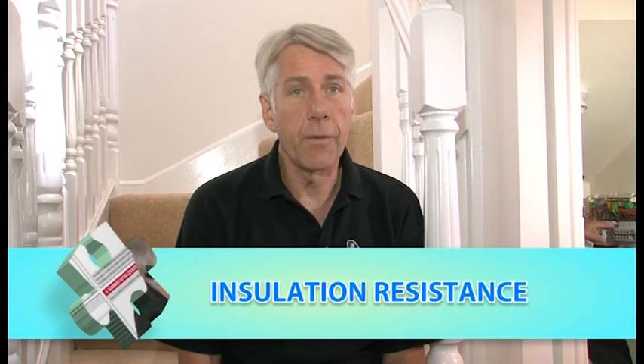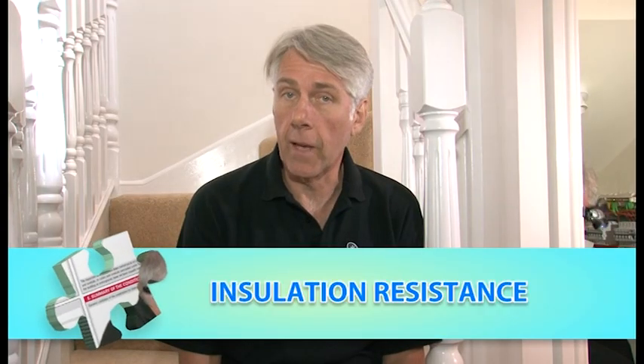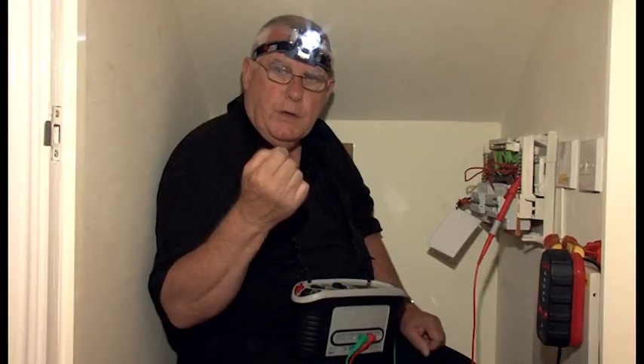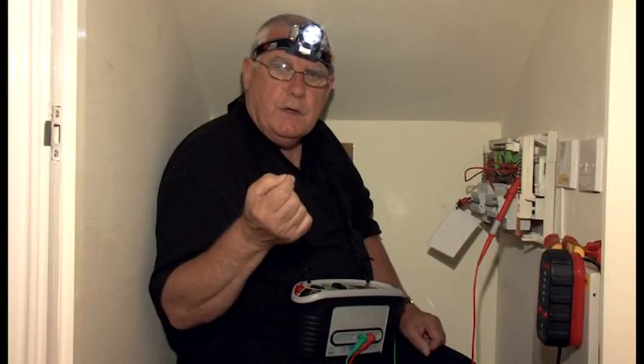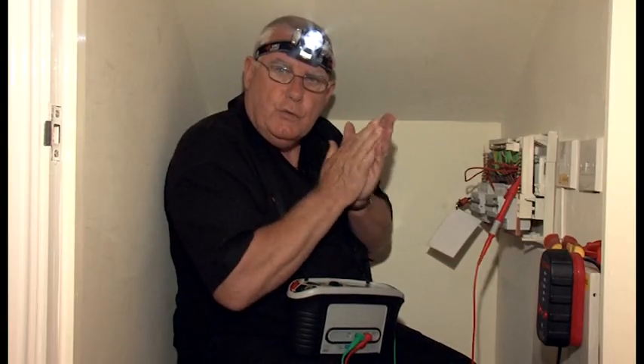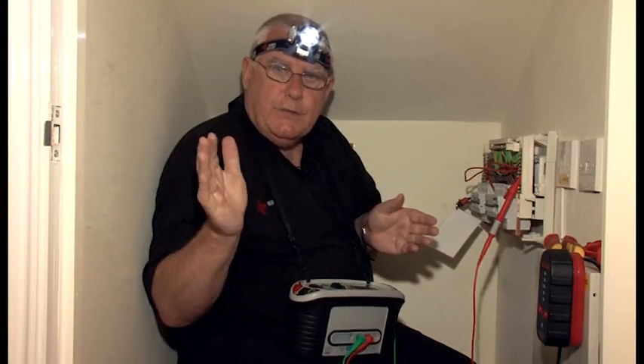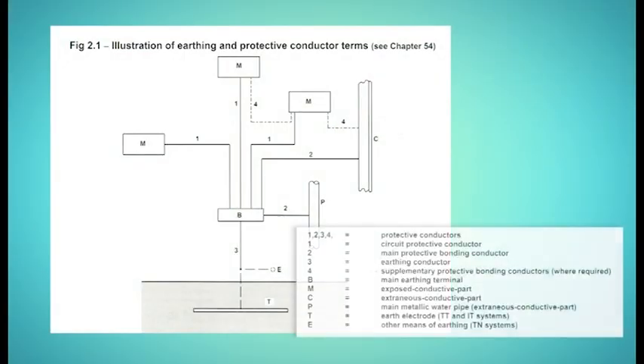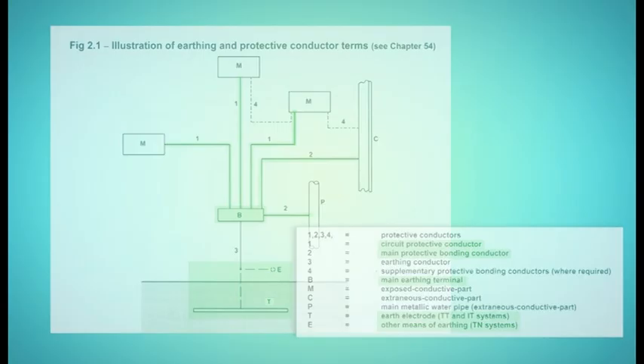Our next test is the final dead test before replacing the cover and switching the installation back on. And this is to check the insulation resistance of the installation. I'm going to undertake the alternative test method, which checks between line and neutral cross-connected together and the earthing arrangement. Remember that the earthing arrangement is the whole thing. So that's the MET with all CPCs and main protective bonding installed and the earthing conductor connected to the means of earthing, in this case in the meter cupboard.